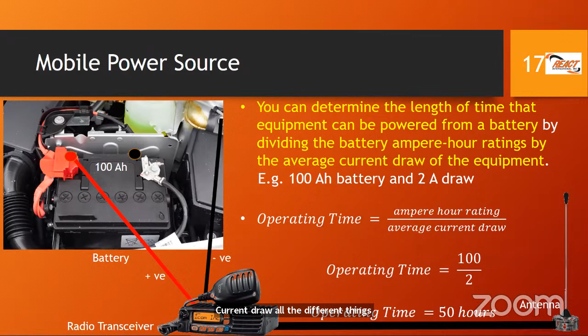So you can determine the length of time that equipment can be powered from a battery by dividing the battery ampere hour ratings by the average current draw of the equipment, which is what we just did in a formula. Right? So how long will the battery last? You find out what the ampere hour rating of the battery is, and you divide that by the current draw or the current consumption, or how much current does this radio use, or the current usage, current draw, all different things, right? All right, let's do a couple more slides before we take our break.